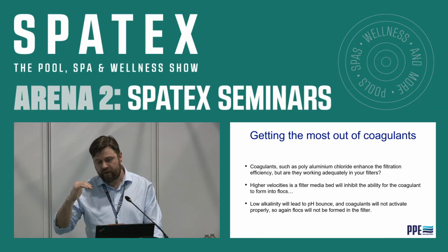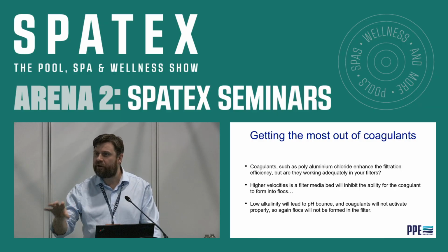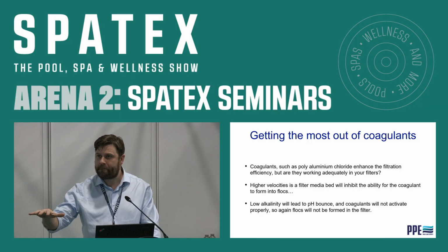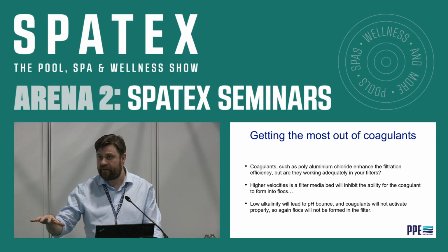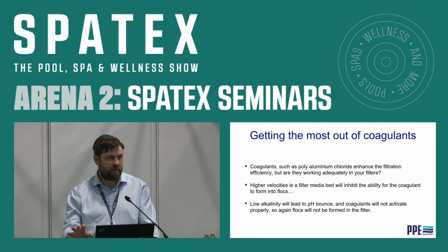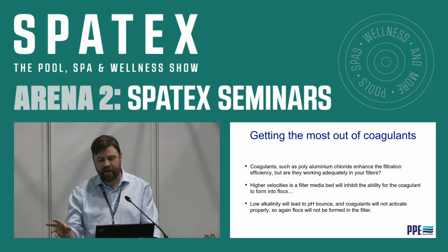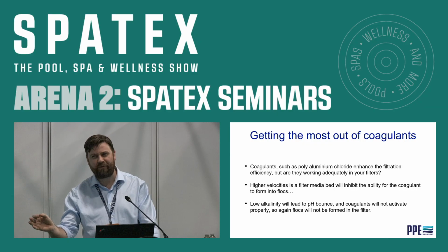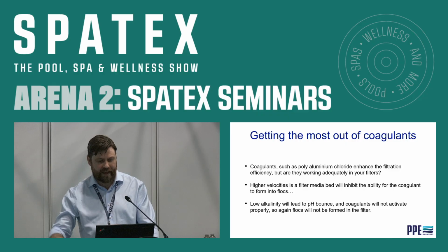If we have higher rate velocities, we're not going to be able to form a floc inside the filter itself. If our water balance is bad, our total alkalinity is all over the place, we're not going to be able to form a floc either. It's got to be just right. Hence, I think, the trade name Goldie Flocks, right? Not too much, not too little, just bang on.